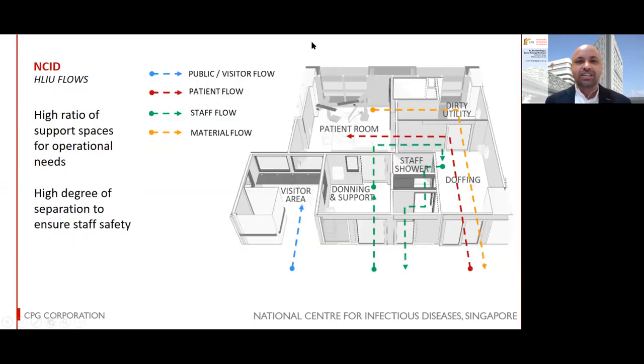To maintain a high degree of separation and allow safe operations, the patient room is supported by extensive support spaces for staff and logistics. The rooms are designed with a strict pressure control regime maintained by interlocking doors.